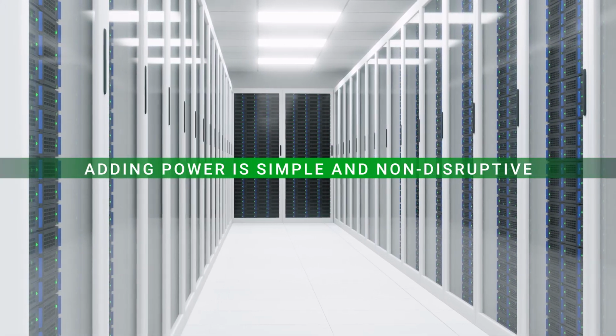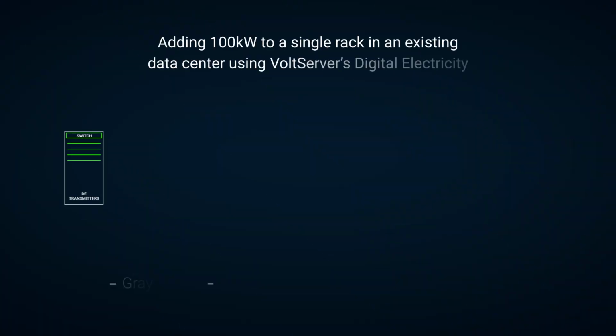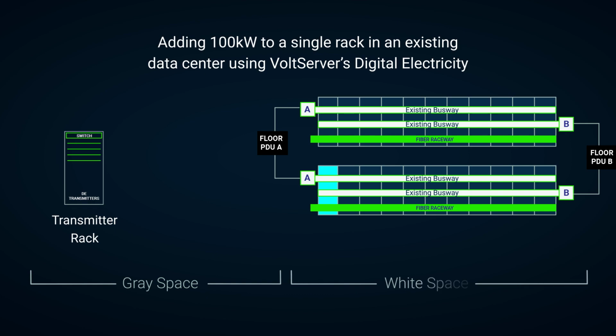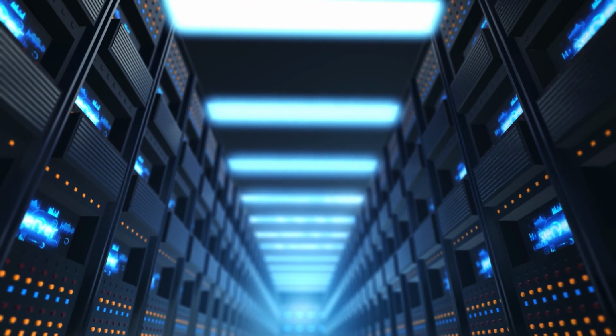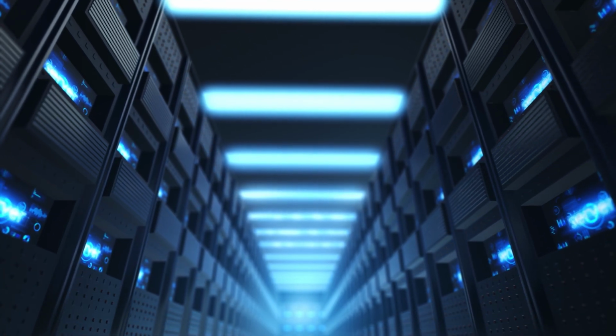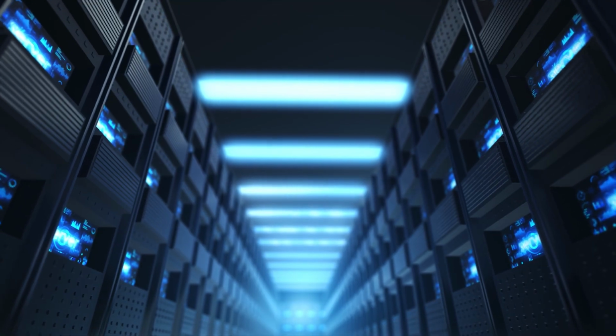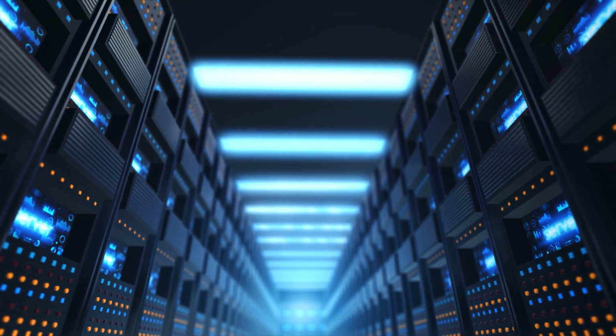With components in hand, starting at the gray space, you add a single transmitter rack using an existing UPS battery, or by including a rack-mounted UPS within the transmitter rack. The configured transmitter rack can deliver hundreds of kilowatts. Additionally, digital electricity can support multiple power types at the server cabinet. High voltage DC is the most efficient option, but lower power density options for AC and 48-volt DC are also available.